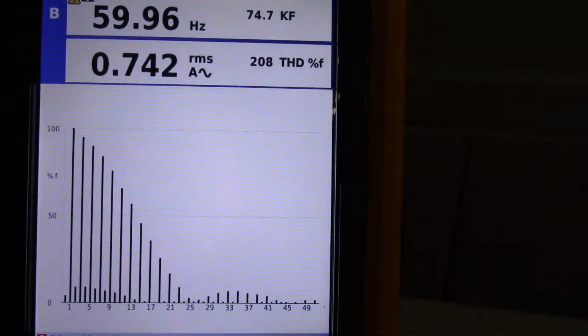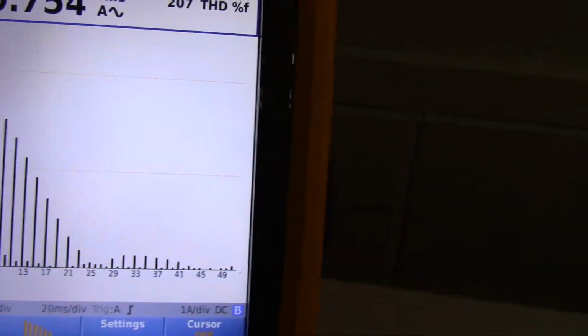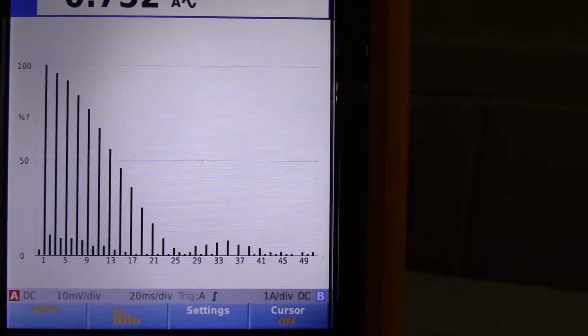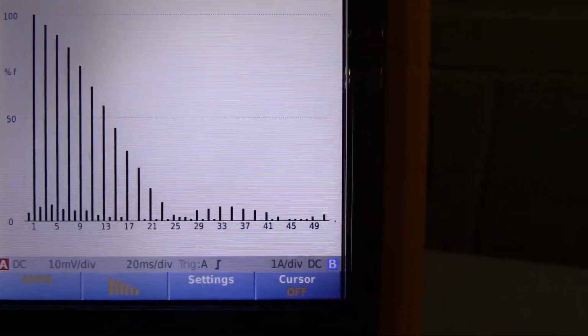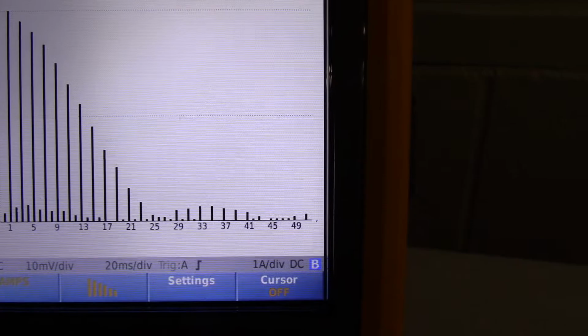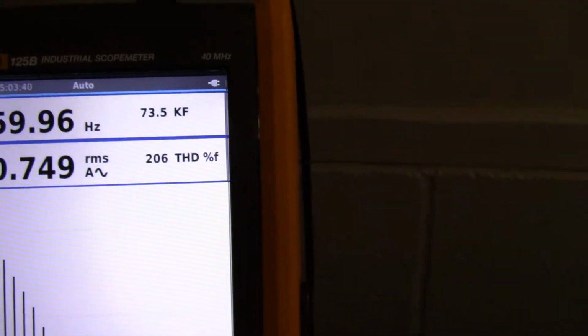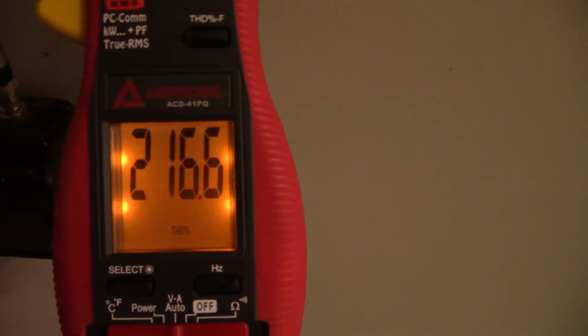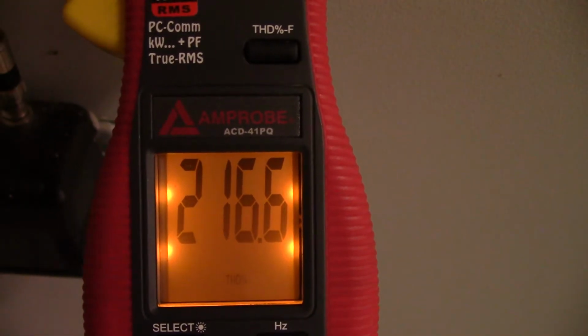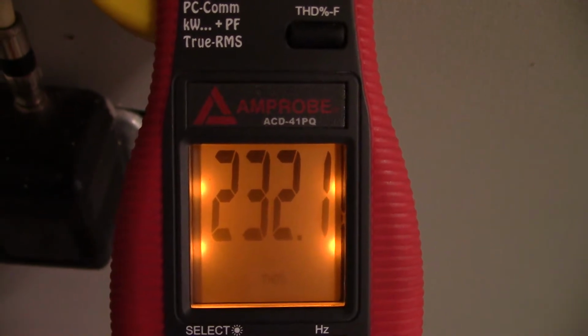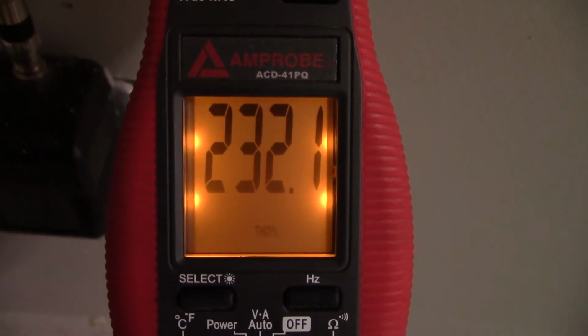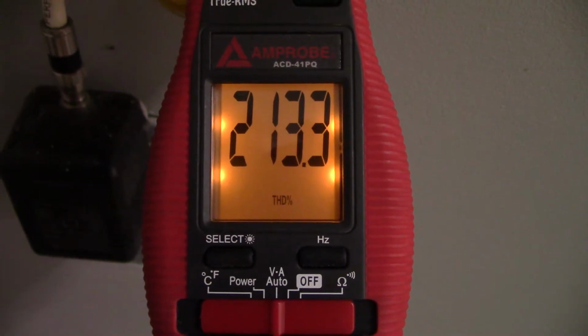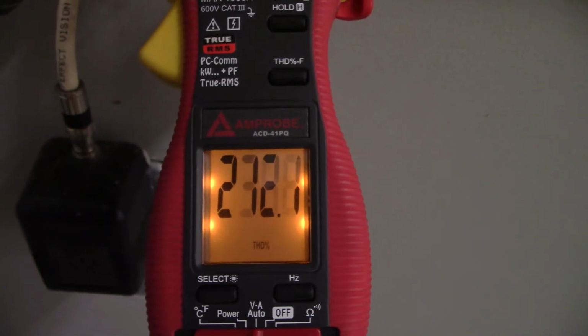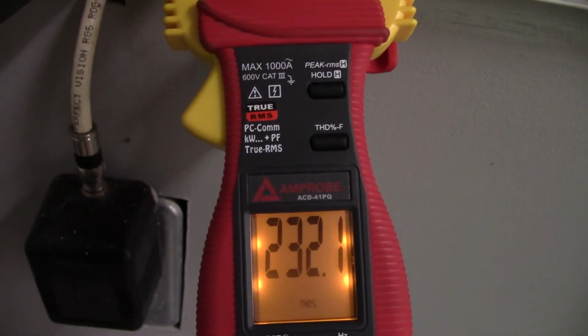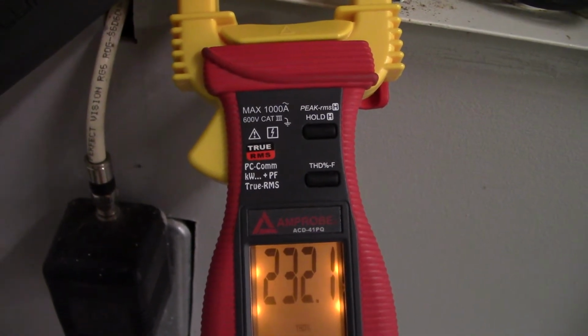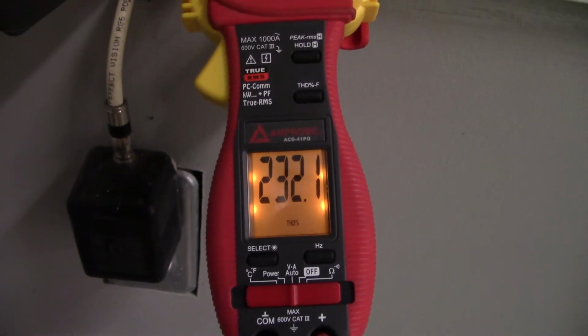Now, the difference between the Amprobe meter and this very expensive meter is this very expensive meter will show you the subcomponents of all the distortion, and I will explain that in another video. I just wanted to compare the two. This meter reads up to the 51st harmonic. It doesn't display the percentage of each harmonic, but it will include those components in the overall distorted value that it reads. So it's a really good, simple meter for troubleshooting harmonics, especially for isolating. If you want to find out if you have a problem in your system, it's a great meter for that.